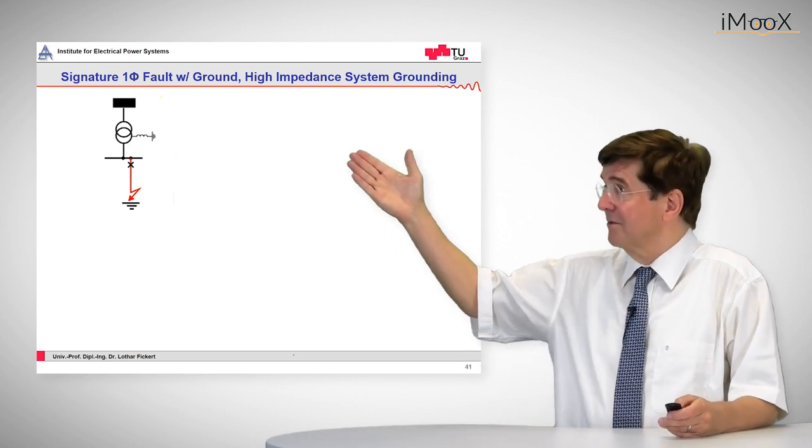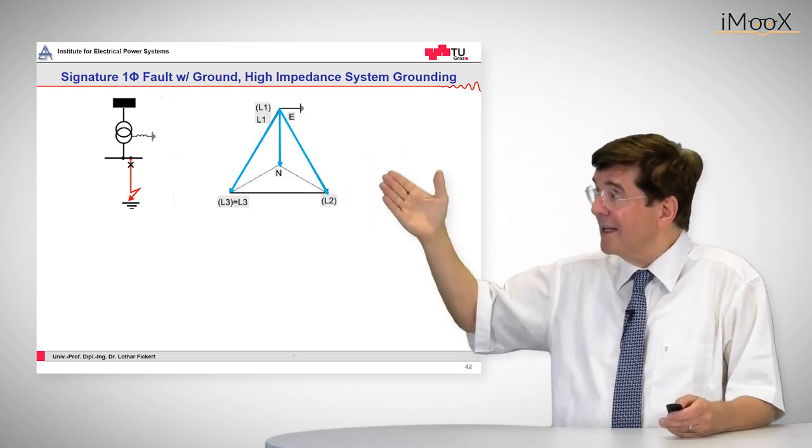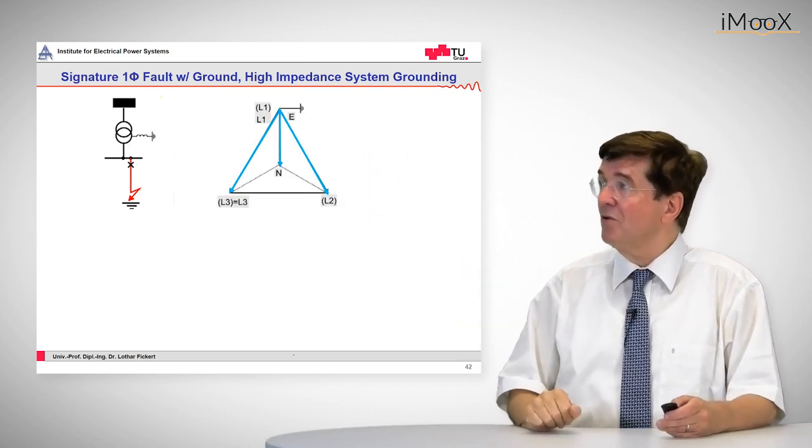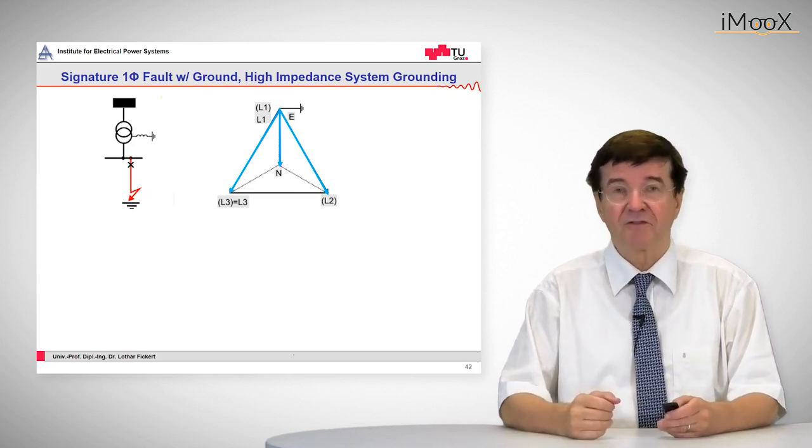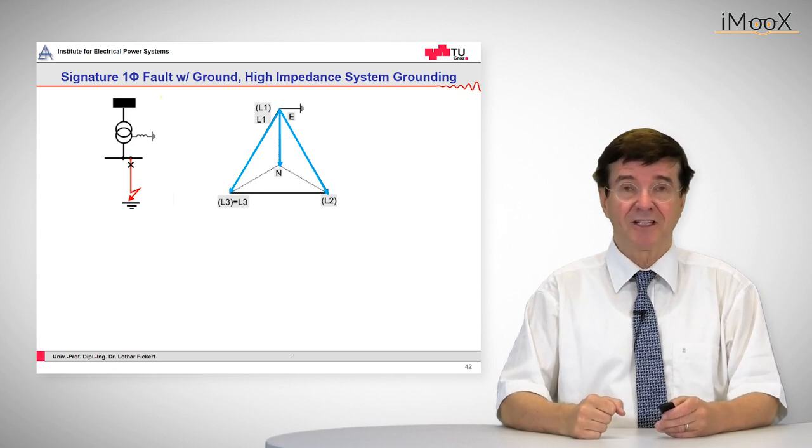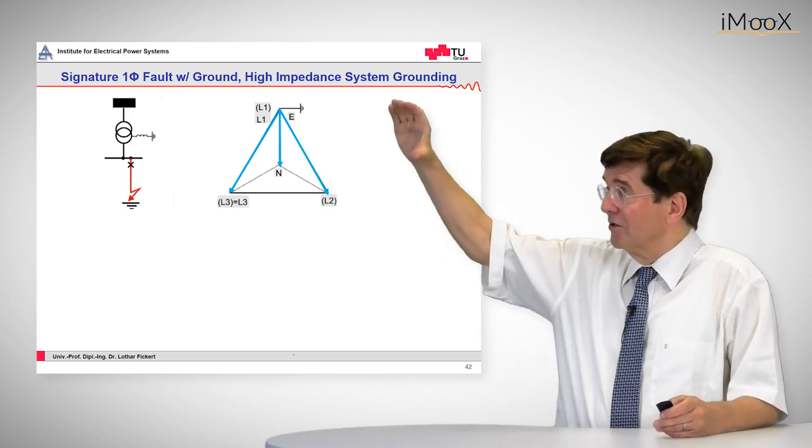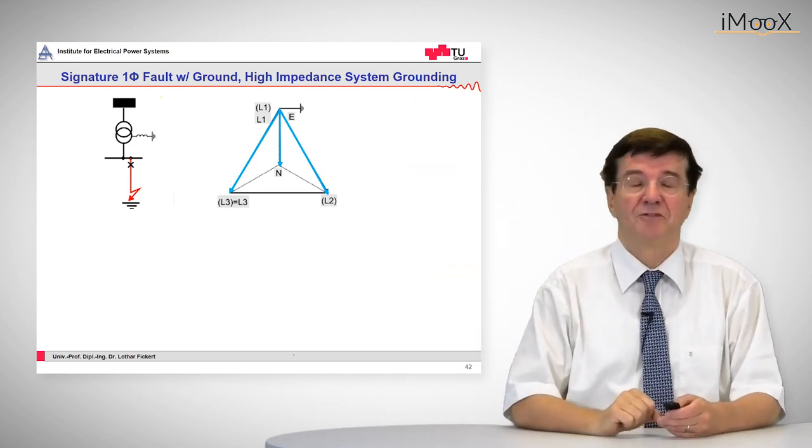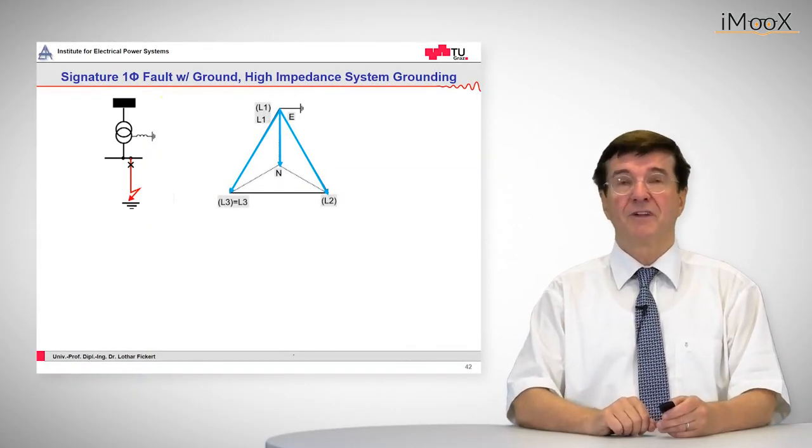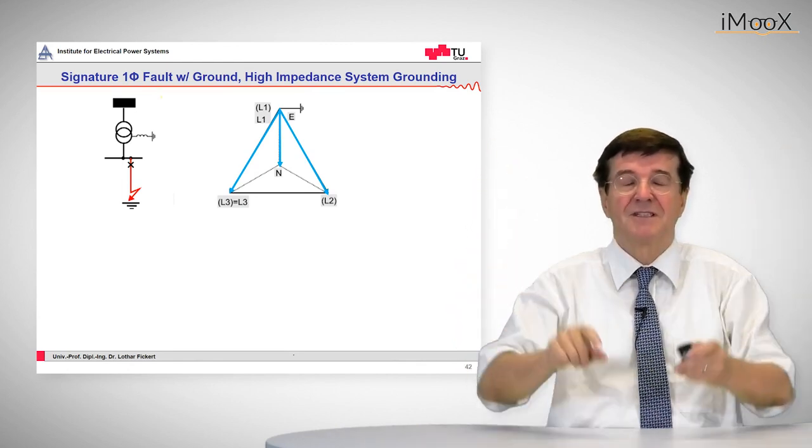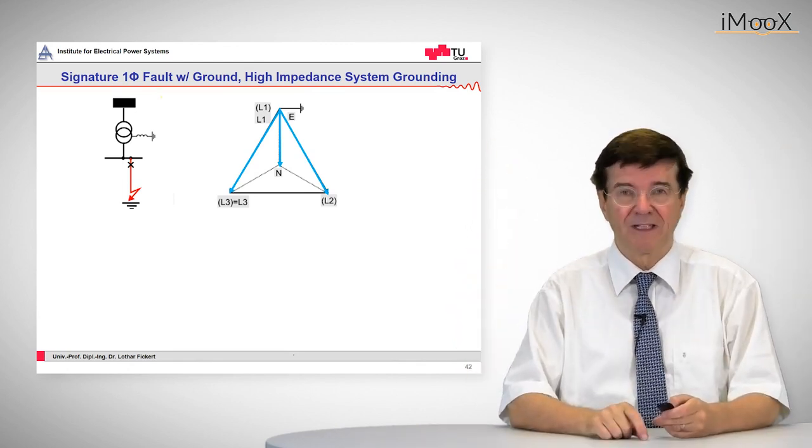Again we start with the appearance of the fault and now we can see that the whole triangle has not changed so much. That means the phase-to-phase voltage remains unchanged, but the whole triangle has moved away from neutral in the sense that L1 has become the neutral and the two other phase-to-ground voltages have risen by a factor of root 3.